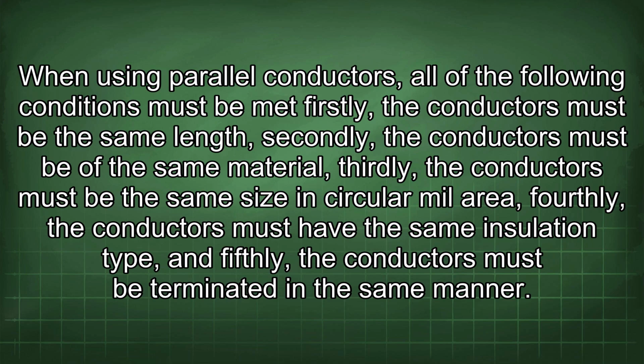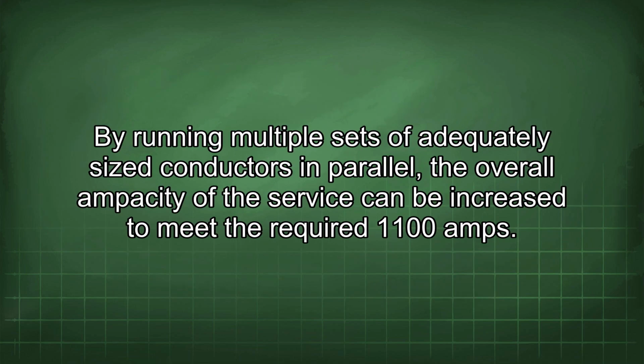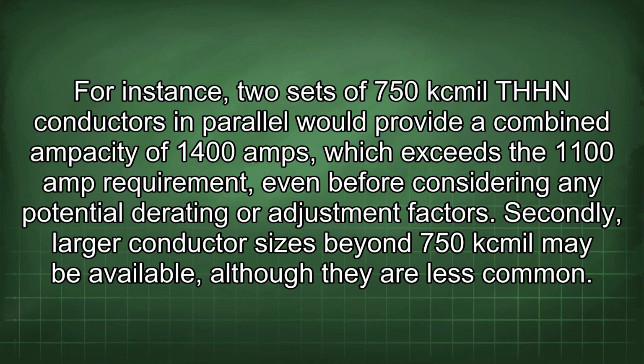Thirdly, the conductors must be the same size in circular mil area. Fourthly, the conductors must have the same insulation type. And fifthly, the conductors must be terminated in the same manner. By running multiple sets of adequately sized conductors in parallel, the overall ampacity of the service can be increased to meet the required 1100 amps. For instance, 2 sets of 750 kcmil THHN conductors in parallel would provide a combined ampacity of 1400 amps, which exceeds the 1100 amp requirement even before considering any potential derating or adjustment factors.